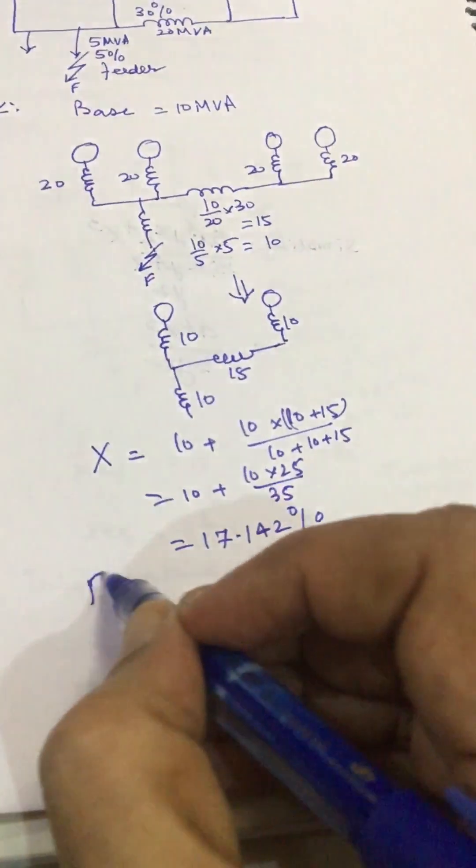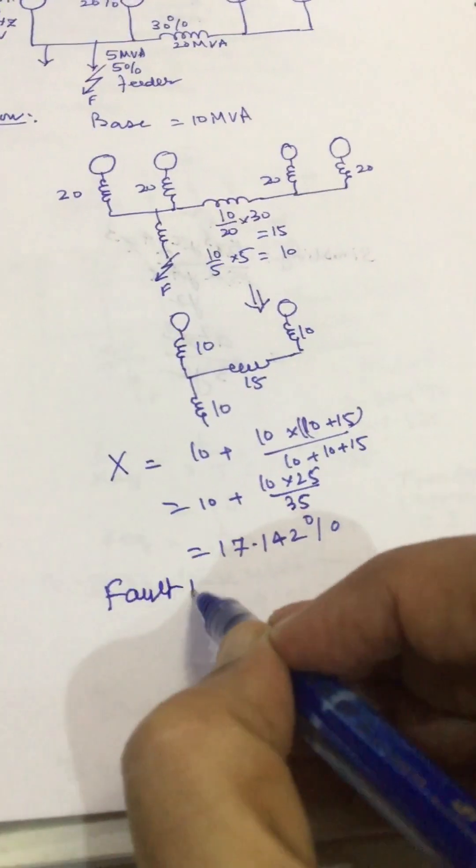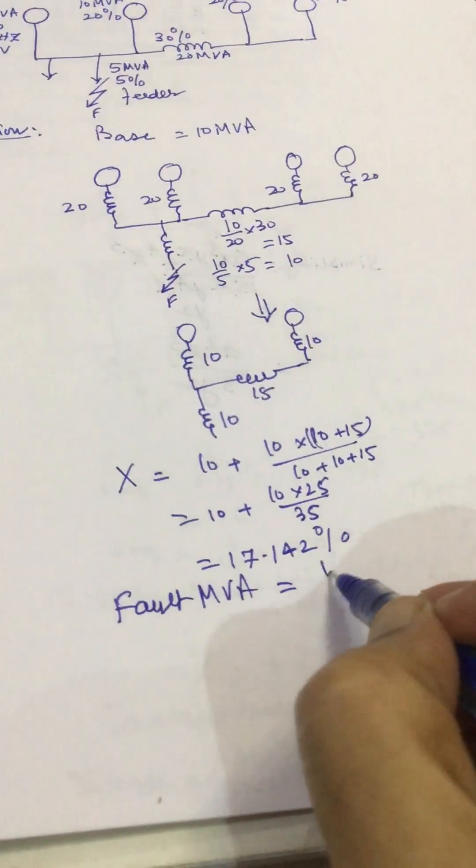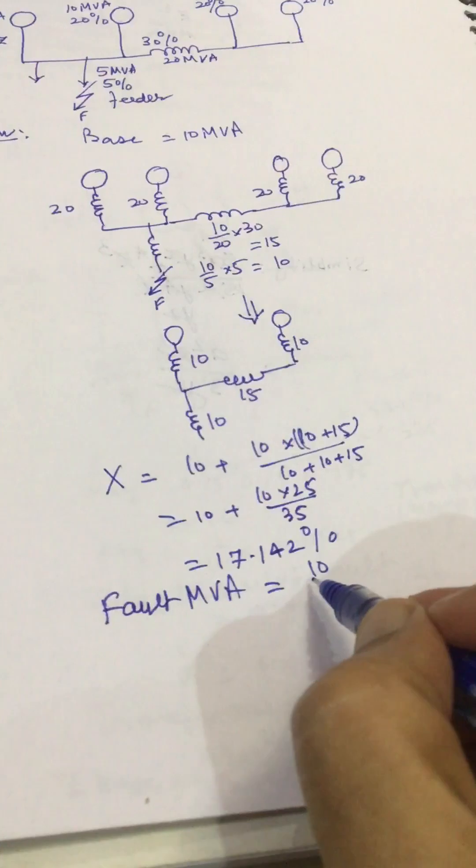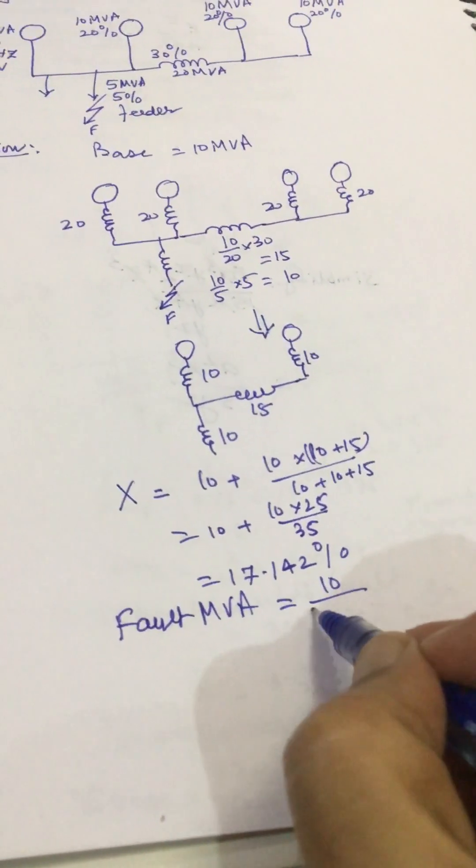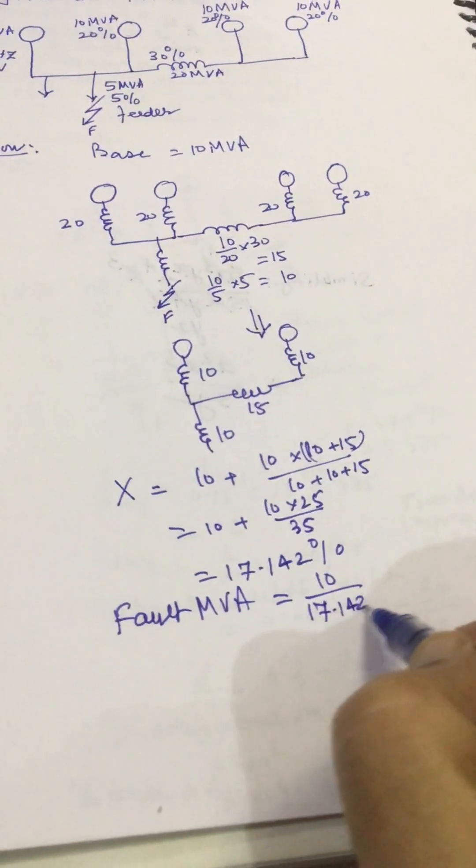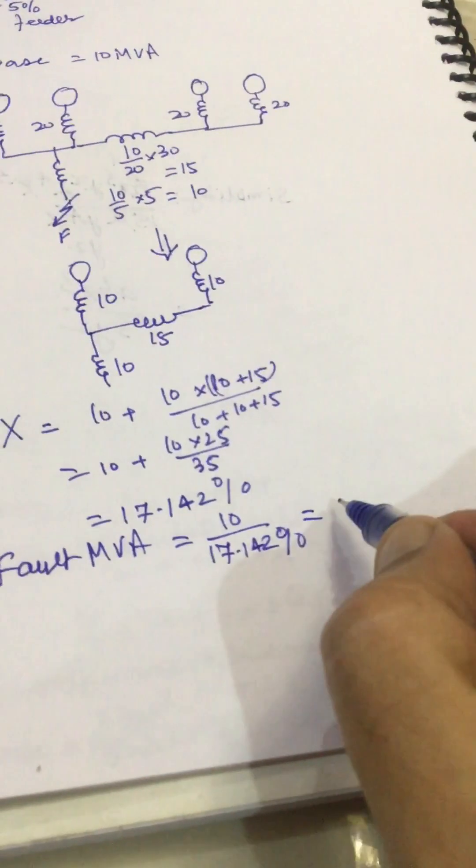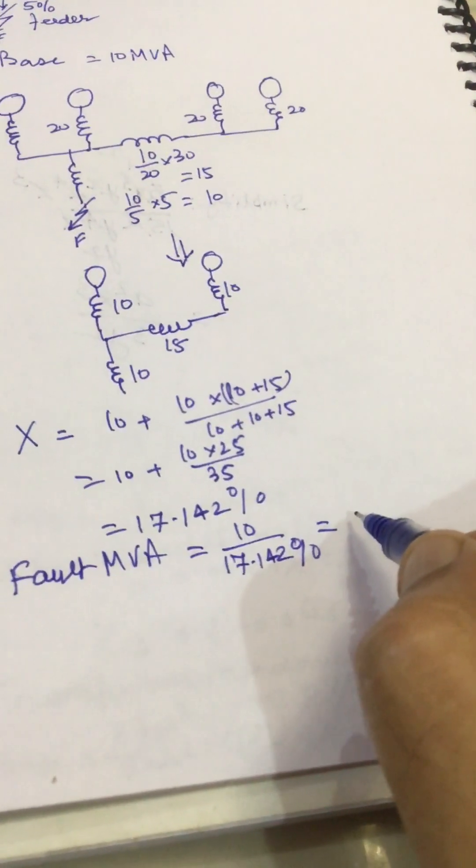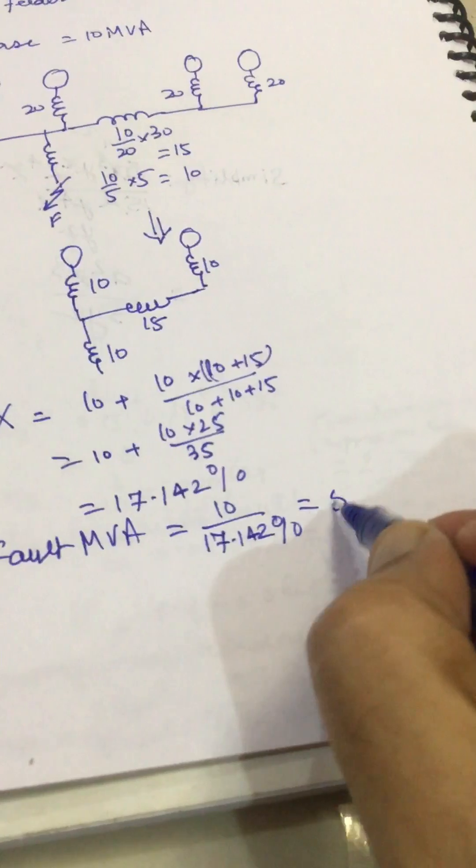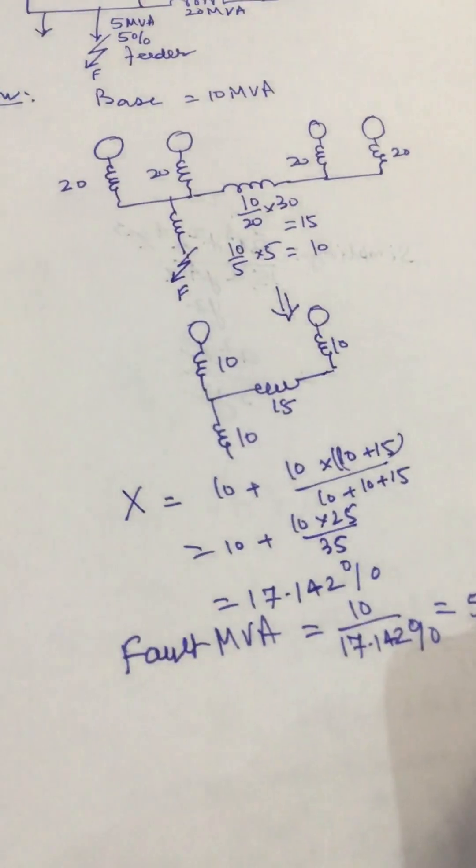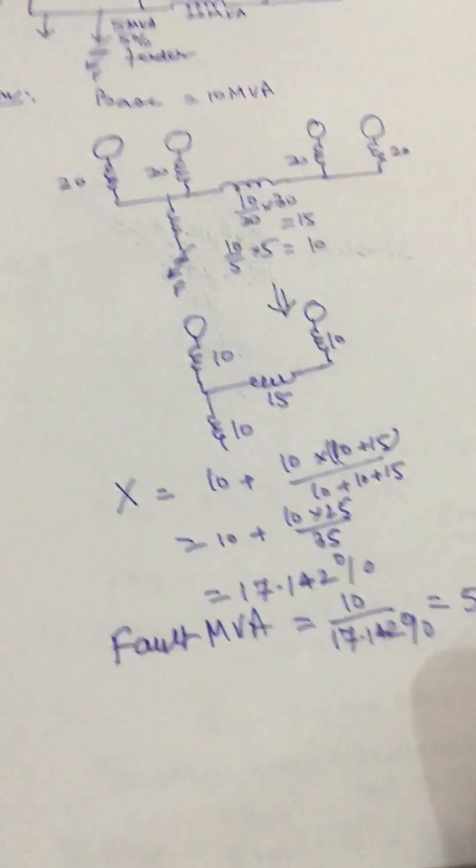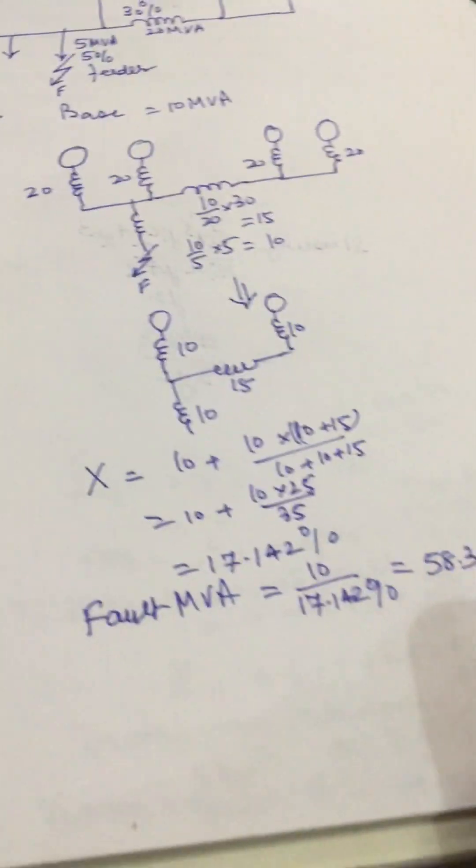Fault MVA we can find out: base MVA that is 10 divided by 17.142 percent and from this we get this as 58.3362.